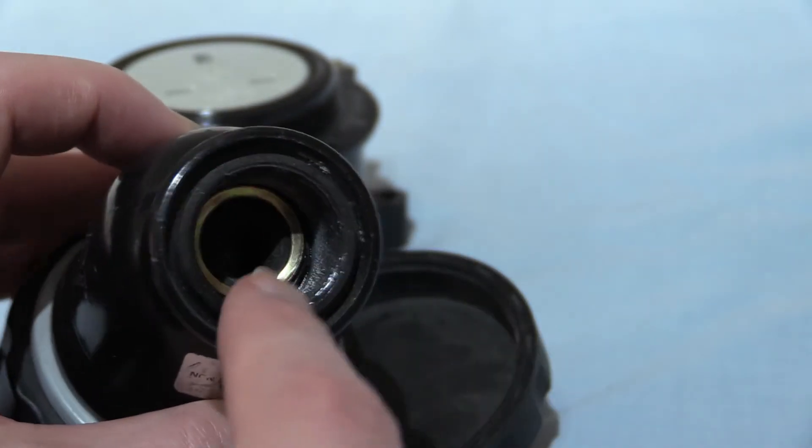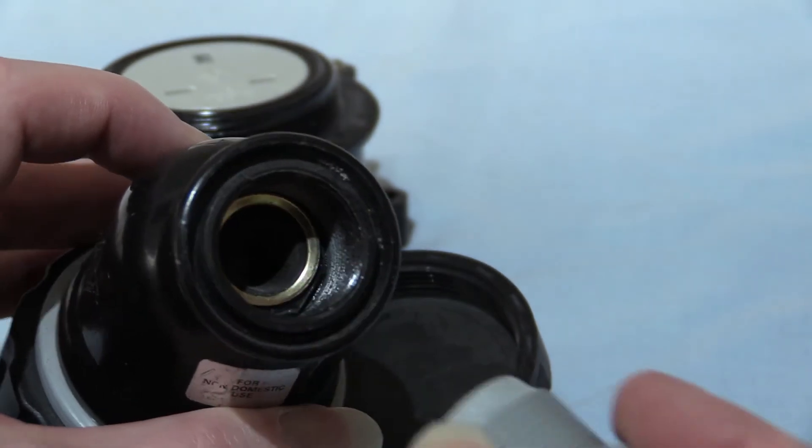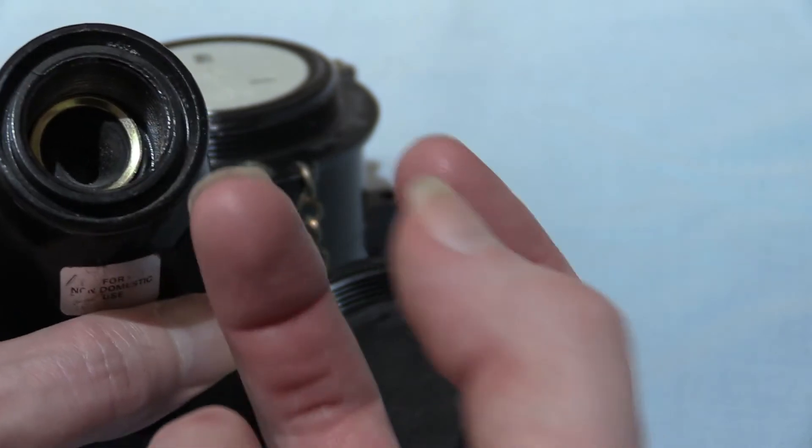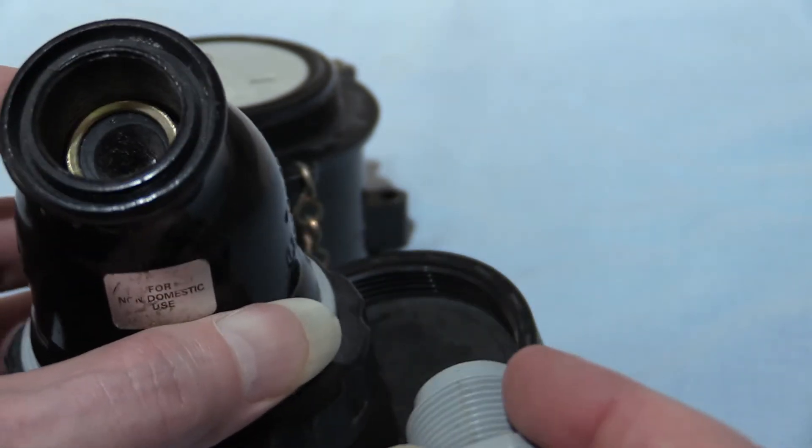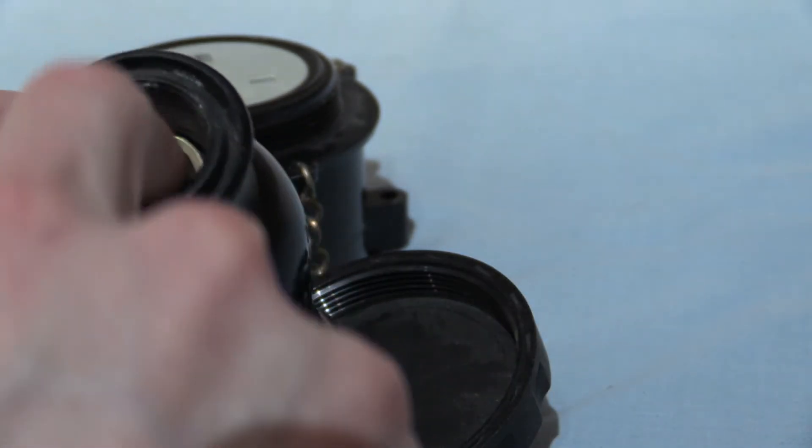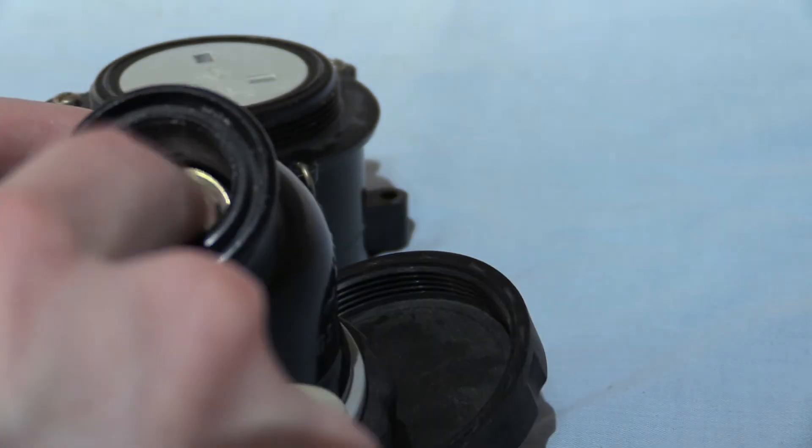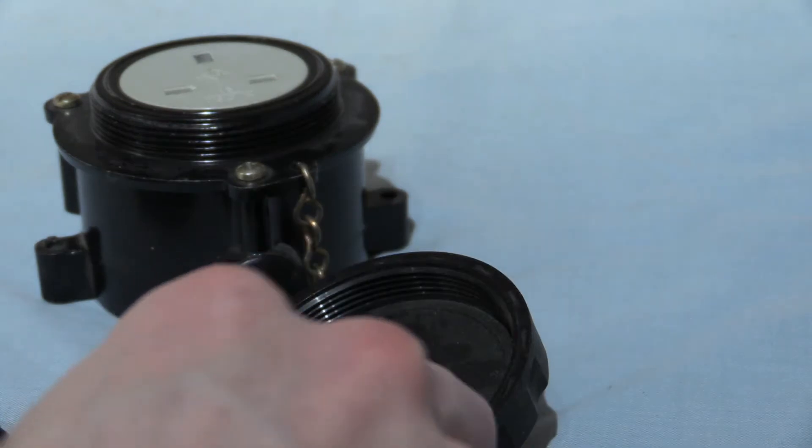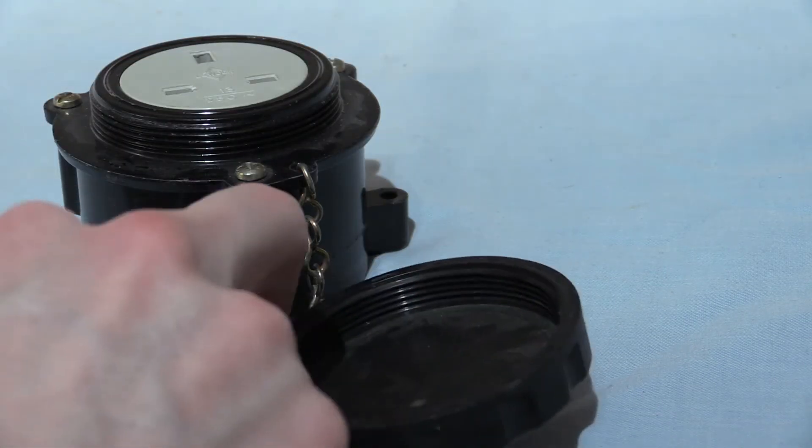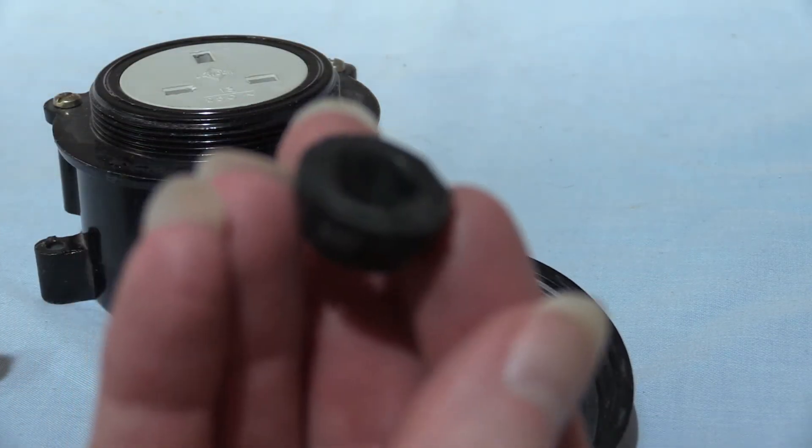When you screw that in there, it presses up against that rubber bung. There you go, you can see the hole in there, how small that is. And as you tighten that down, it presses up against that metal little ring in there, squashes that in there, and as it does so, the hole closes up and grips the flex.